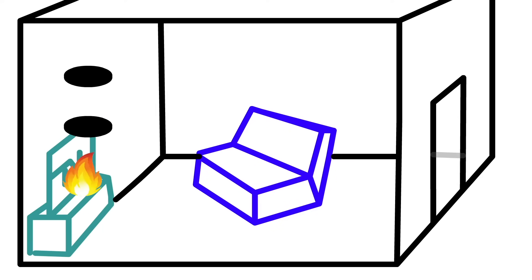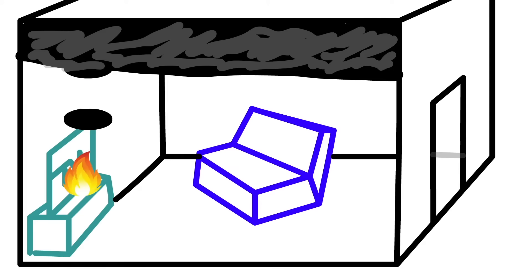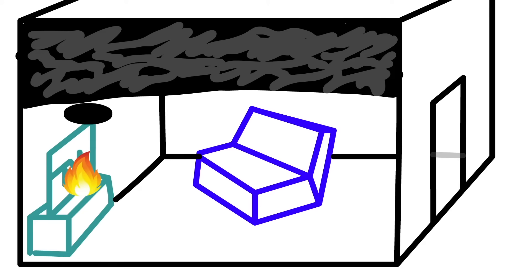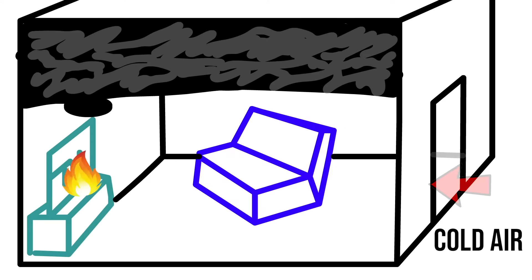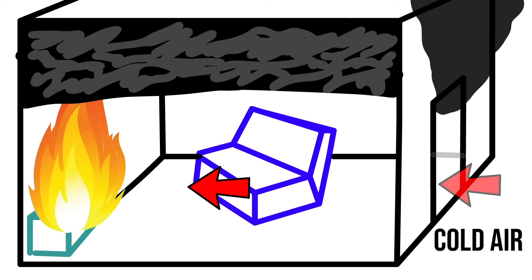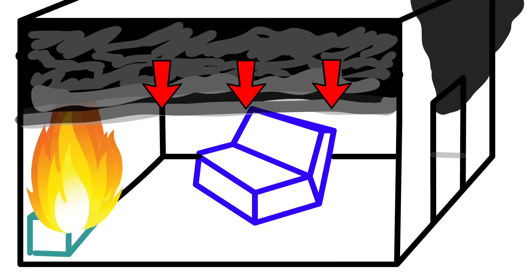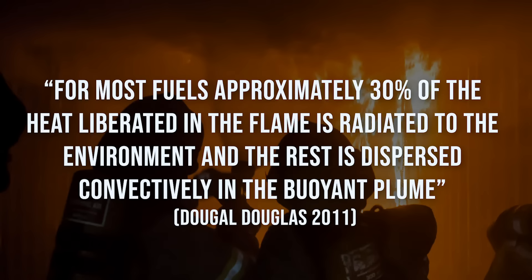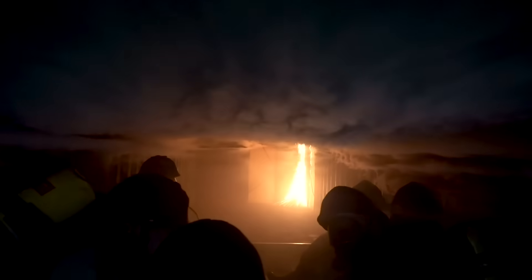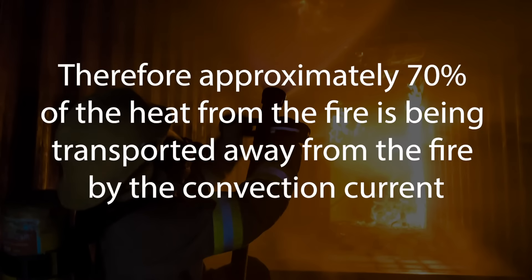The heat comes from the fire itself. As it burns, it pushes heat, smoke and flame into the overpressure area. By the process of convection, that heat spreads across the room and can start to move into other rooms. We see cold air drawn in through the door while smoke pushes out through the top. Approximately 30% of the heat liberated in the flame is radiated to the environment, while the remaining 70% is dispersed convectively in the buoyant plume — meaning 70% of the heat is transported up and away, available to heat other objects throughout the building.